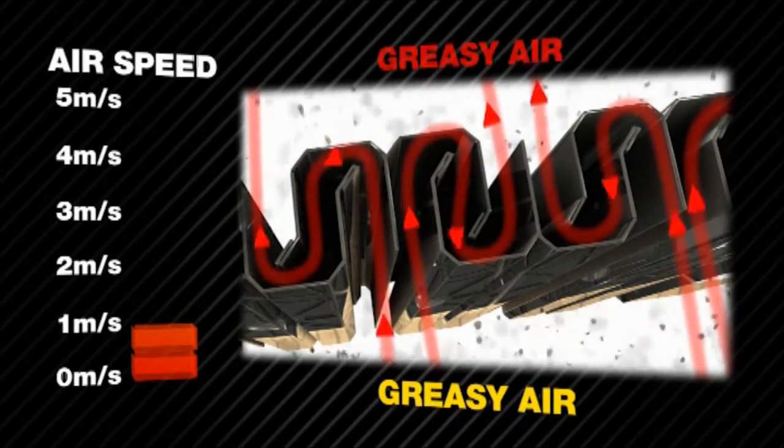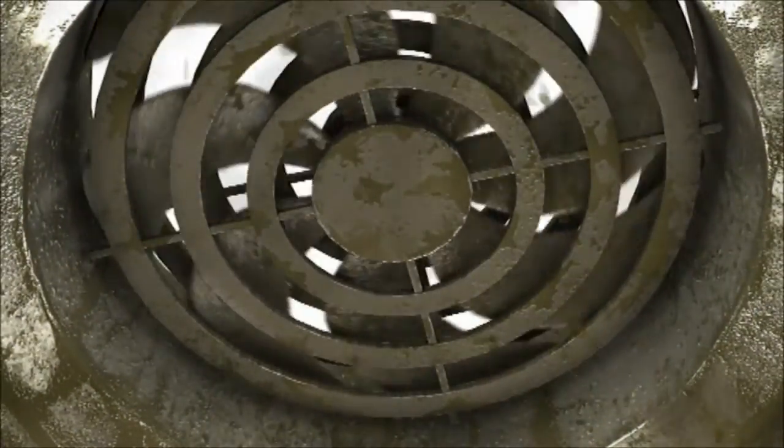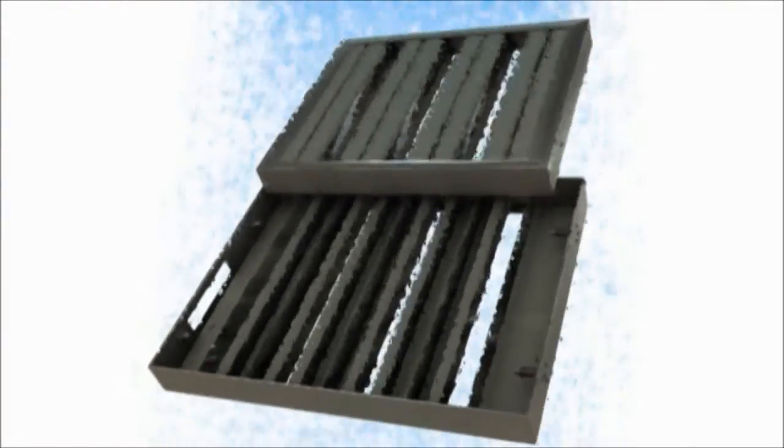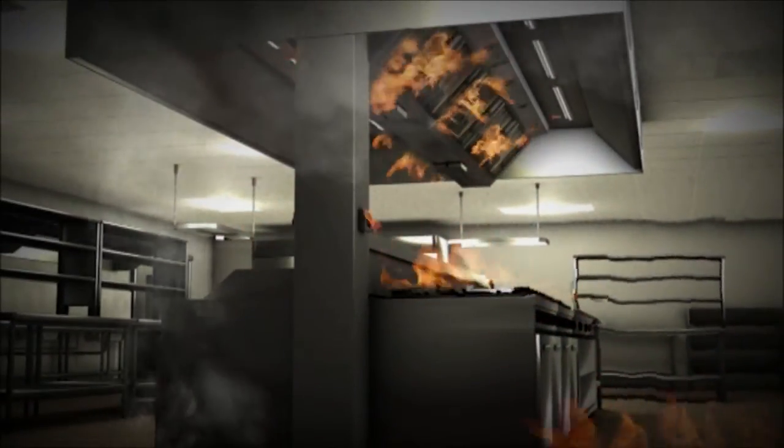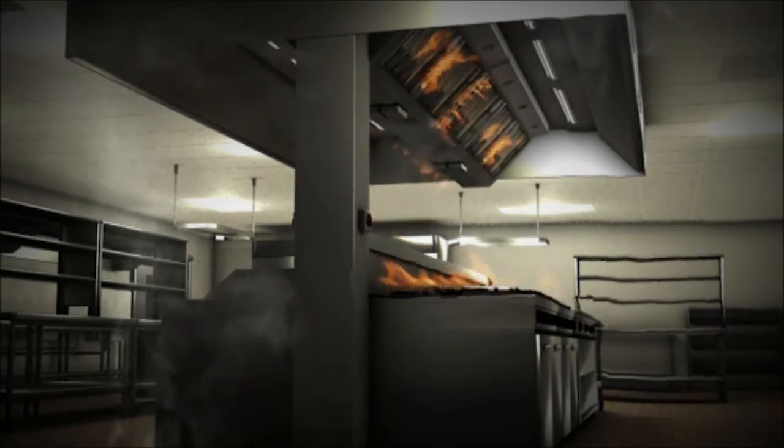With the filter becoming far less efficient, many more grease particles pass through, coating the ductwork and fans, which could increase the need for expensive maintenance and more frequent cleaning. More importantly, grease lined ductwork creates a potential fire risk, which could destroy your building or endanger lives if it were to ignite.